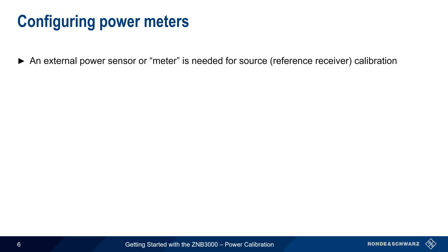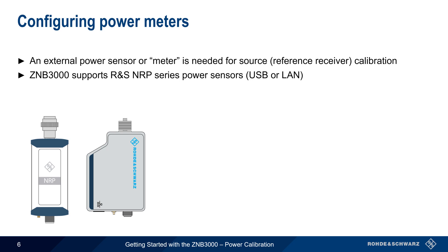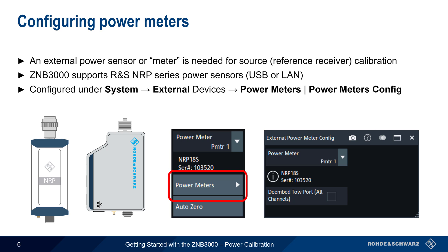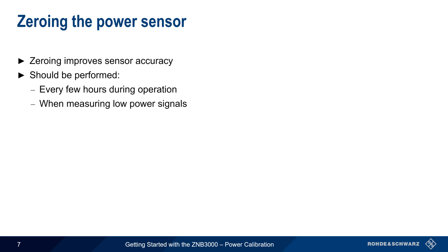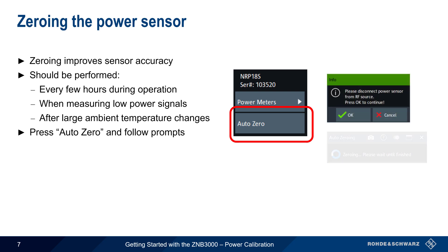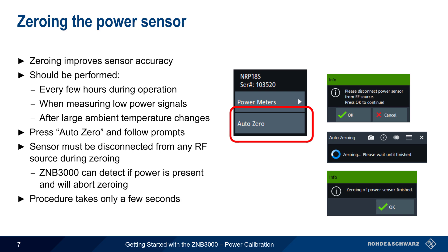An external power meter is needed when performing source or reference receiver calibration. The ZNB3000 supports most Rohde & Schwarz NRP Series power sensors, including both USB and LAN models. These devices are selected and configured under System External Devices, then either Power Meters or Power Meters Config. Zeroing the selected power sensor will improve sensor accuracy and should be performed every few hours under normal conditions, but is particularly important when measuring lower power signals or after a large change in ambient temperature. Press Auto Zero and follow the prompts to start zeroing. The sensor must be disconnected from any source of RF power during zeroing, but the ZNB3000 will automatically abort the test if it detects power is present at the sensor.